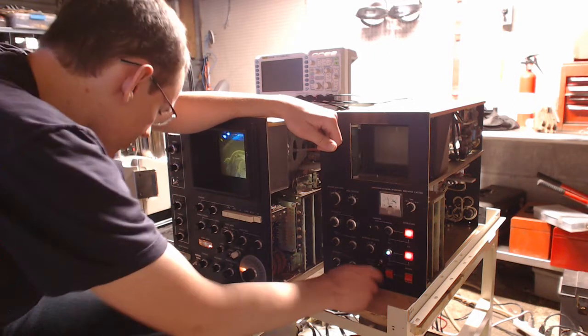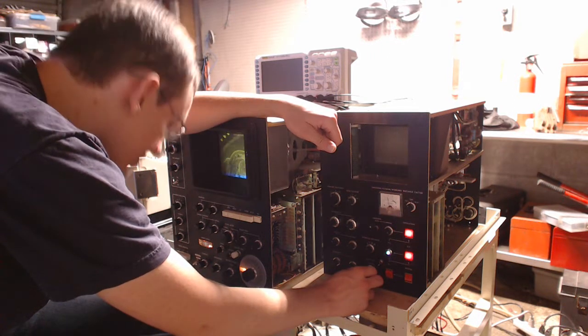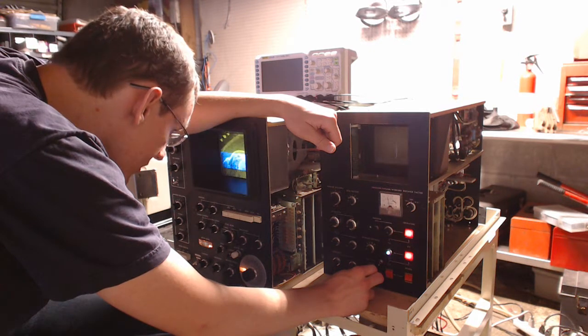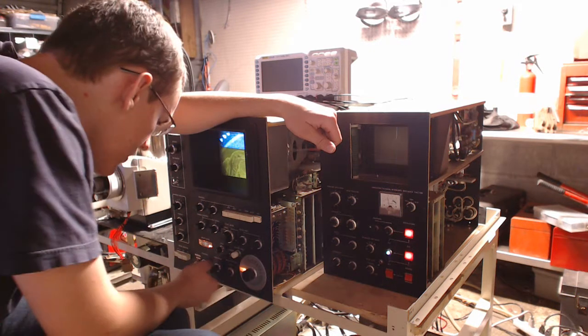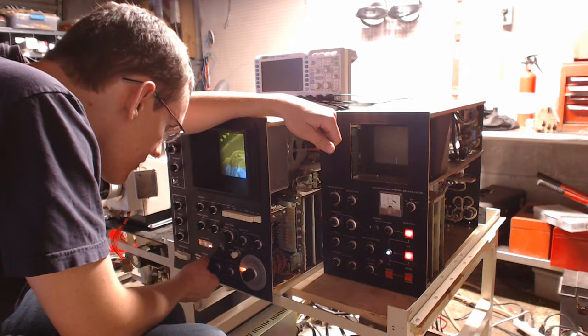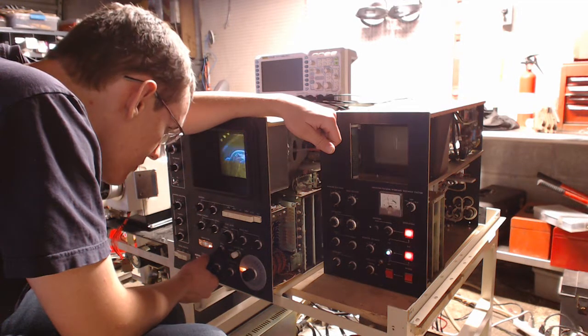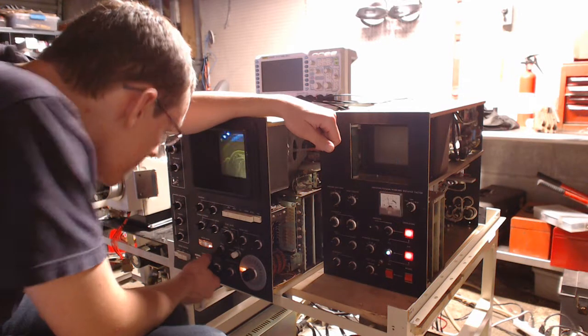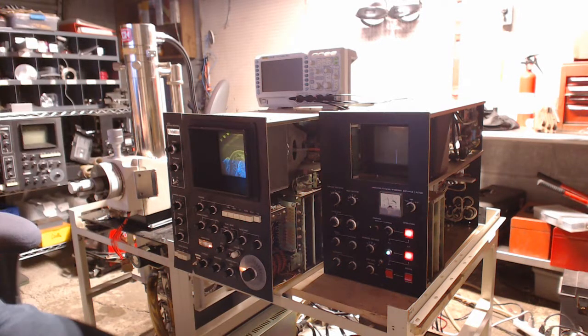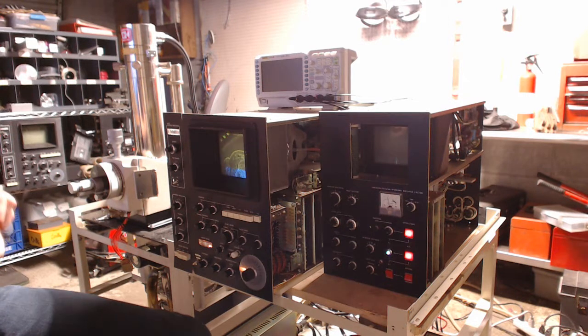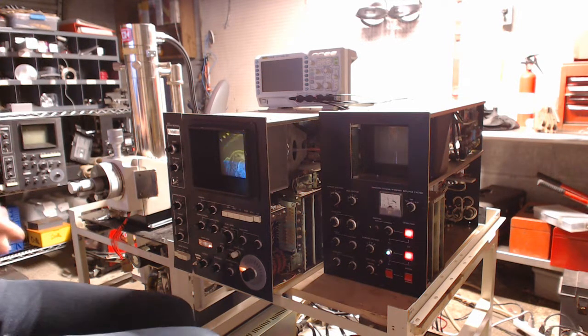I'm running into some performance limitations with the Scintillator right now. Does that show up as a dynamic range issue? No, it shows up as a noise issue. Like we saw before, that 1 megahertz noise that comes in there? No, this is more of a spot noise. Because you just start getting more random returns with the degraded Scintillator, and so I'm just having trouble identifying what's the edge and what's the noise.